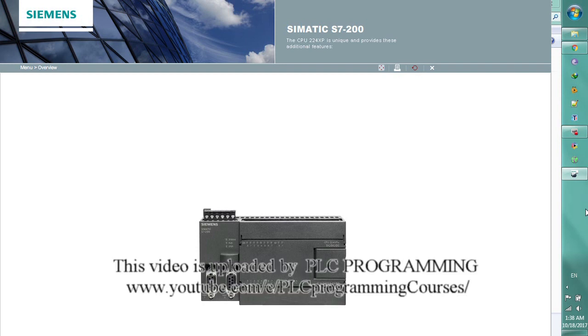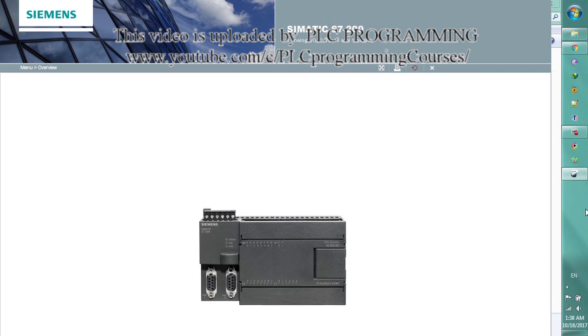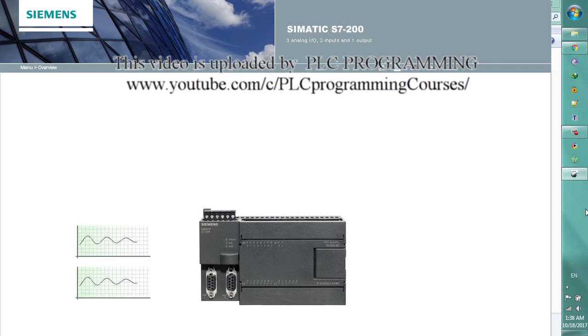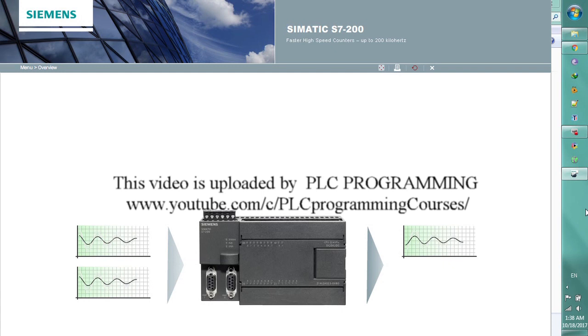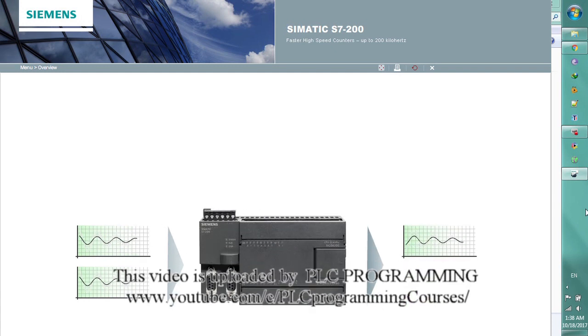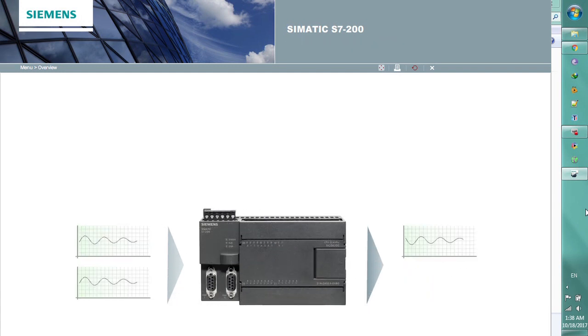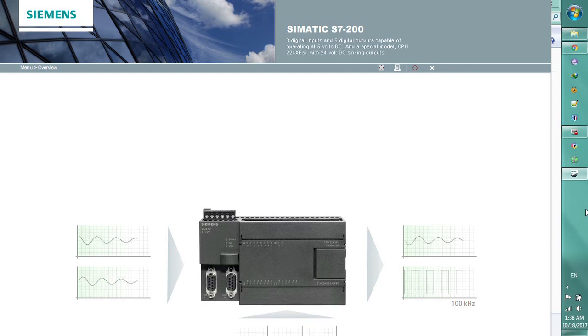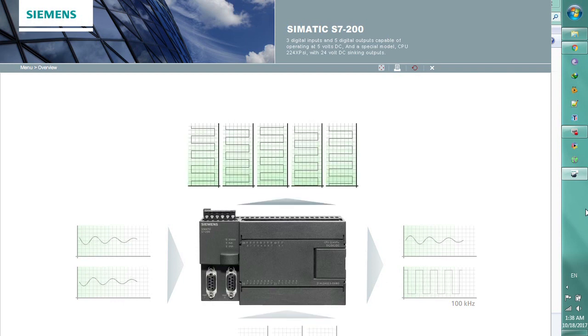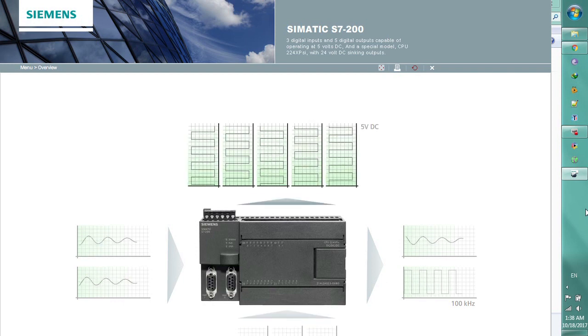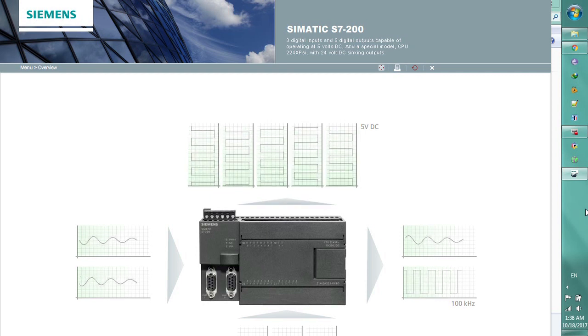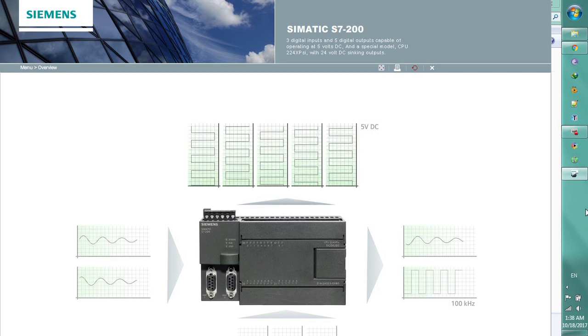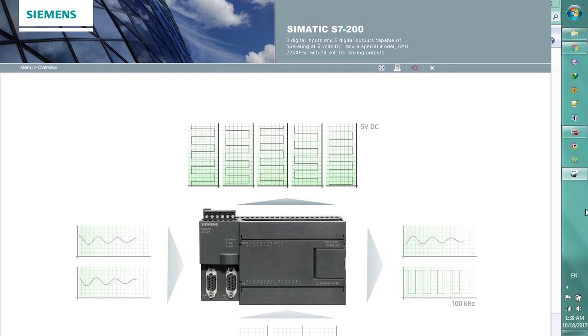The CPU 224 XP is unique and provides these additional features: three analog I.O., two inputs and one output; faster high-speed counters up to 200 kHz; faster high-speed outputs up to 100 kHz; three digital inputs and five digital outputs capable of operating at 5 volts DC; and a special model, CPU 224 XP-SI with 24 volt DC sinking outputs.